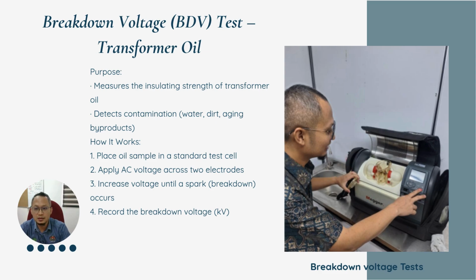To assess the insulating strength of transformer oil, we perform a breakdown voltage, or BDV, test. This test checks the oil's resistance to electrical breakdown by applying voltage across two electrodes until a spark occurs. The breakdown voltage is an indicator of the oil's health. Low BDV values suggest poor insulation and increased risk of failure. Healthy transformer oil should have a BDV greater than 30 kV.